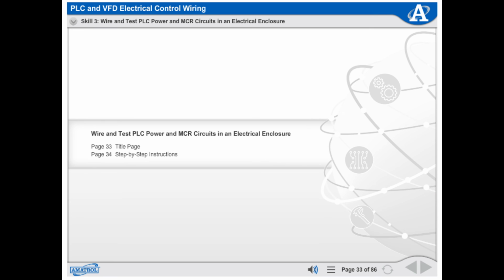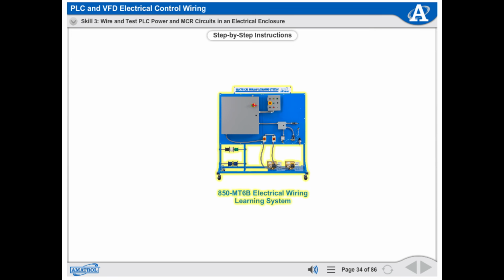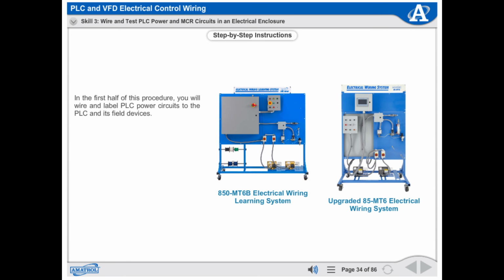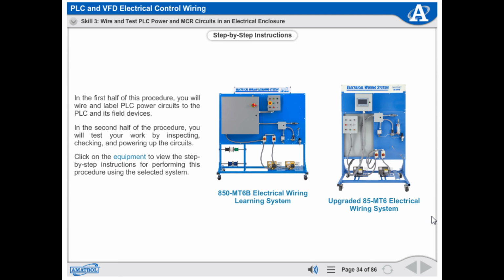Wire and test PLC power and master control relay circuits in an electrical enclosure. In the first half of this procedure, you will wire and label PLC power circuits to the PLC and its field devices. In the second half of the procedure, you will test your work by inspecting, checking, and powering up the circuits. Click on the equipment to view the step-by-step instructions for performing this procedure using the selected system.